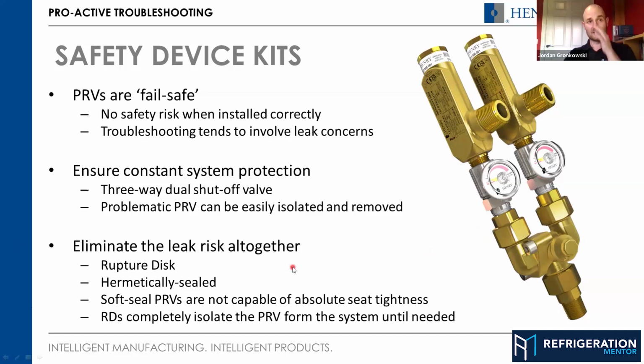And the second thing you can do again for proactive troubleshooting is the second part of this assembly, which is the rupture disc. Now, rupture discs are, for those of you who don't know, a way of hermetically sealing a system, but still having the ability to relieve pressure. So it's a disc in this plate. In this case, it could be nickel, it could be different materials, but it's scored with a laser and very finely tuned so that it bursts at a specific set pressure. And the set pressure of the disc is tied to the set pressure of the PRV, so they both work in unison.